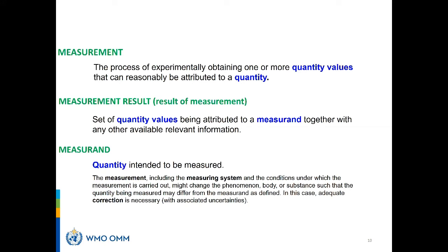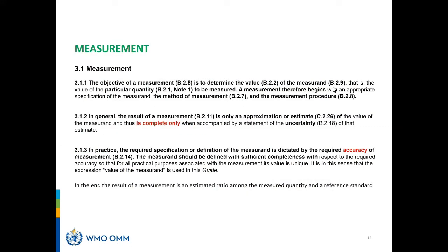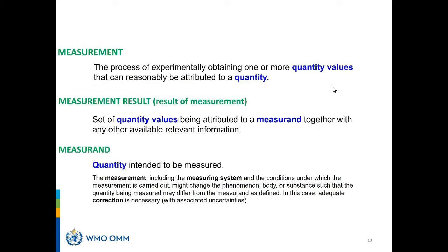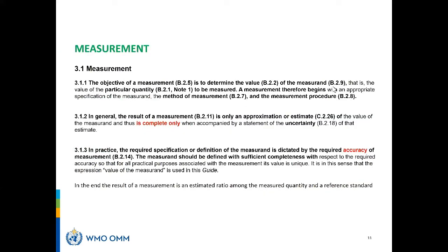So why did I start with these three? Measurement, of course. The measurement result is what comes out of the instrument, but the measurement includes the measuring system, which can also be part of the measurement result. And it can require some correction to be sure that the measurement result is linked to the correct interpretation of it. But we will see that with the uncertainty. Okay, this is how the VIM presents the measurement. We have seen the definition, process of blah, blah, blah. And I just want to touch the notes. The VIM has this numbering. Please don't be afraid of B2, 5B, blah, blah, blah, because it is just a recall from one to the other. You bounce, it's quite easy to do.